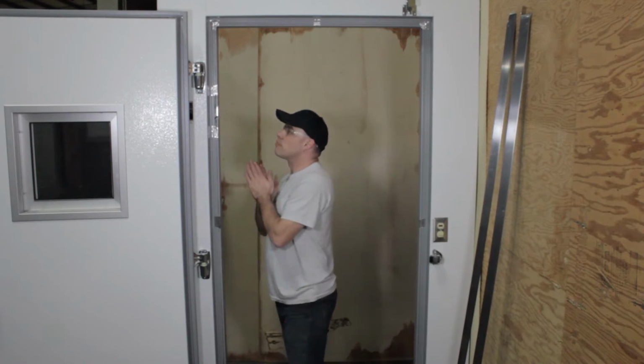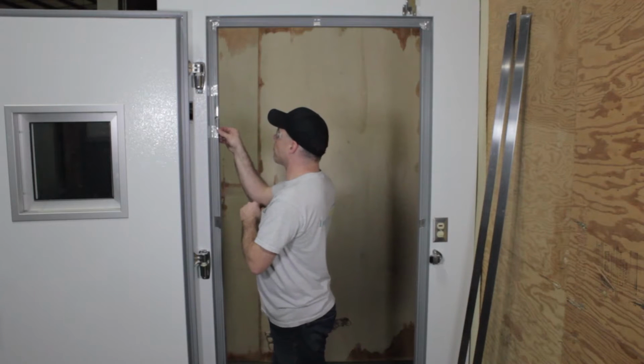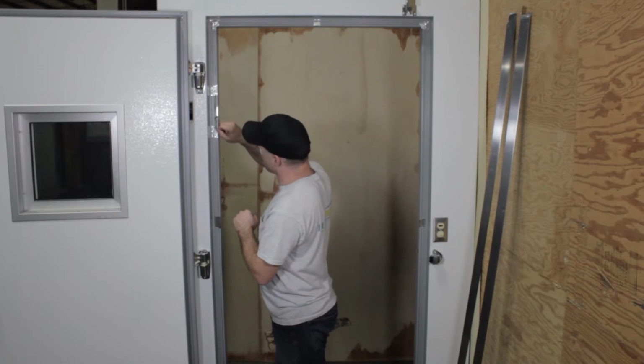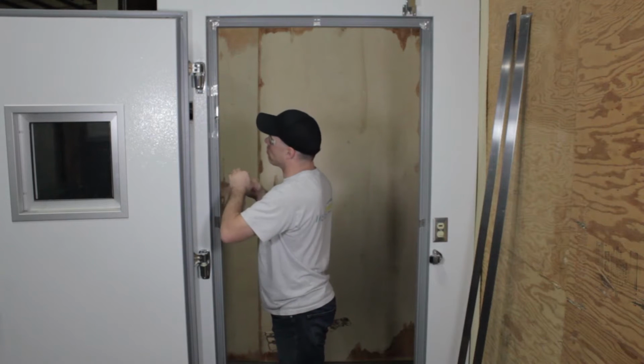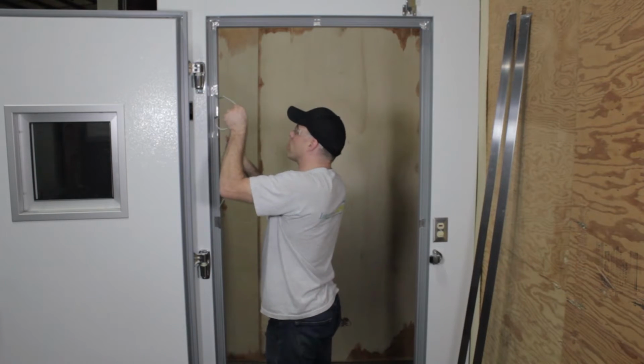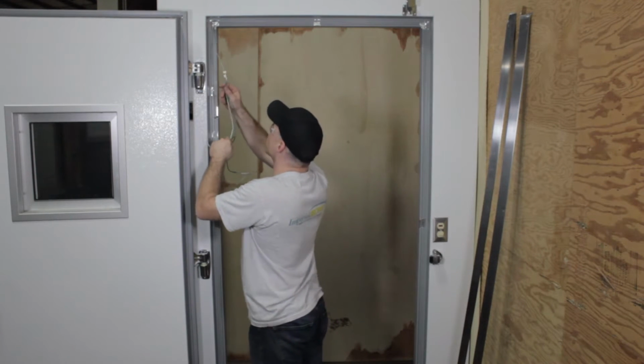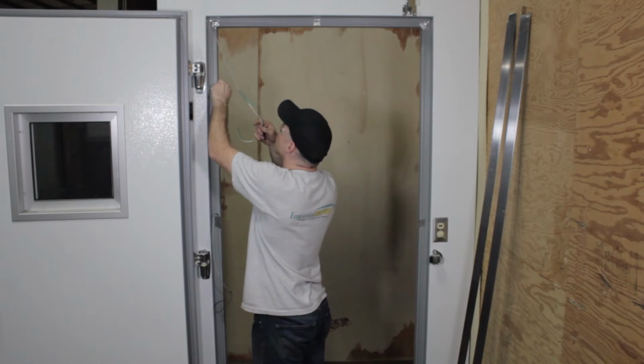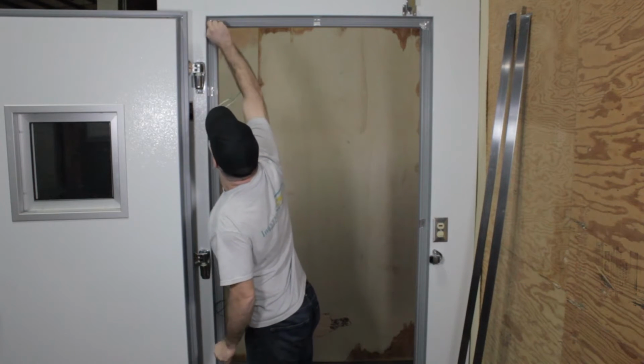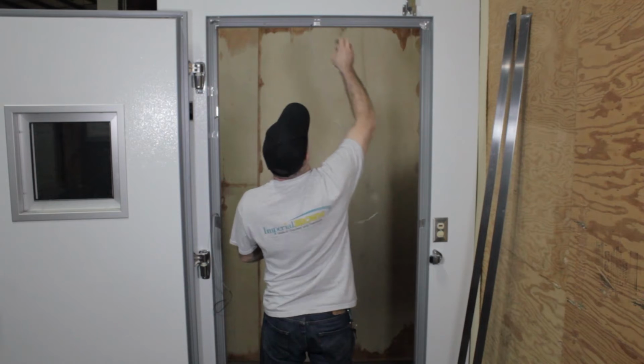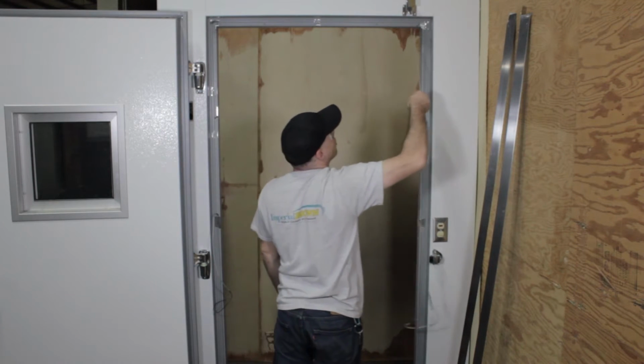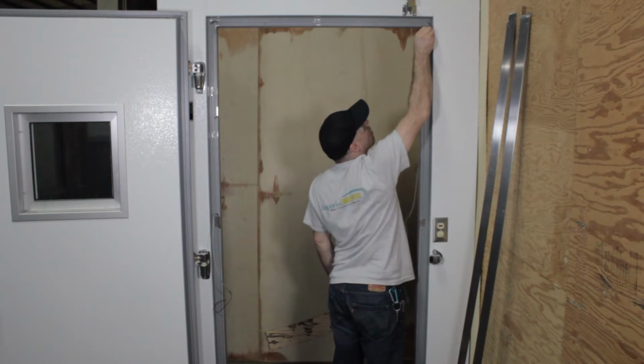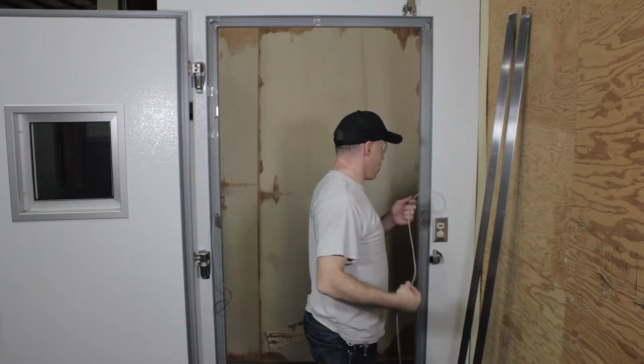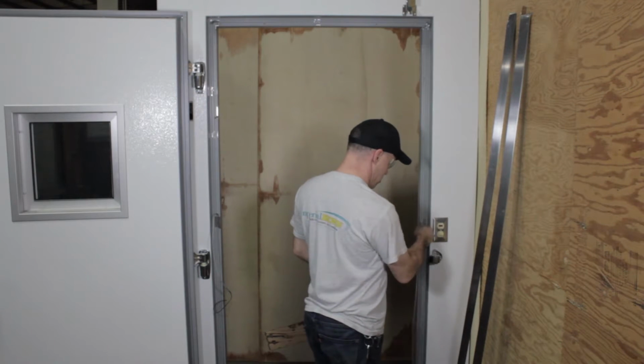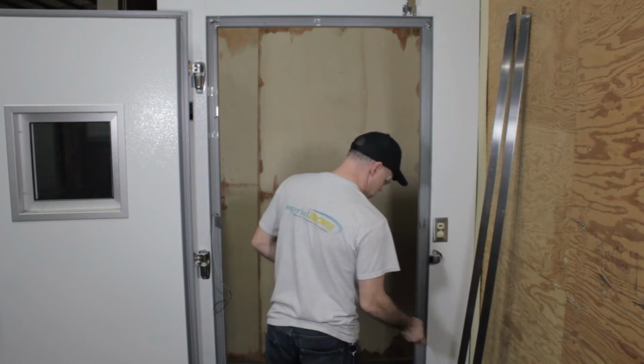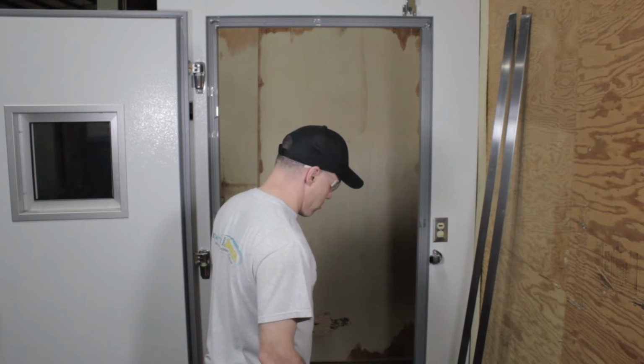Now remove the metallic tape holding the heater cable in place and cut the heater cable electrical wires at the door frame. Here's tip number 1. Leave the wires protruding from the frame and the junction box. You can use these later for a faster completion during electrical hookup. Continue removing metallic tape and the heater cable from around the door until the old heater cable is entirely removed.